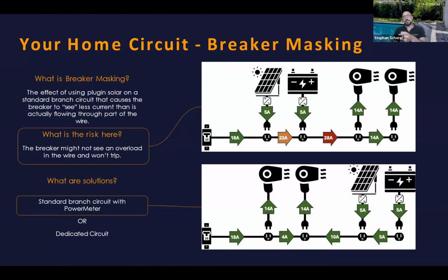And here the NEC says there is a case where you could be overloading this small subsection of that wiring by simply pushing power where we're already pulling power, therefore overloading the wire. And the thing is, the breaker only measures in one direction, so it will not necessarily know that a fault is happening. And that's called breaker masking, when it doesn't see what's happening 100%. So the NEC says, well, in theory, if you plug it in correctly, as in the lower picture, that risk is gone essentially. But you cannot ask from your everyday consumer to know this, or frankly, in my experience, even from electricians, that they know exactly which outlet is where on a branch circuit.